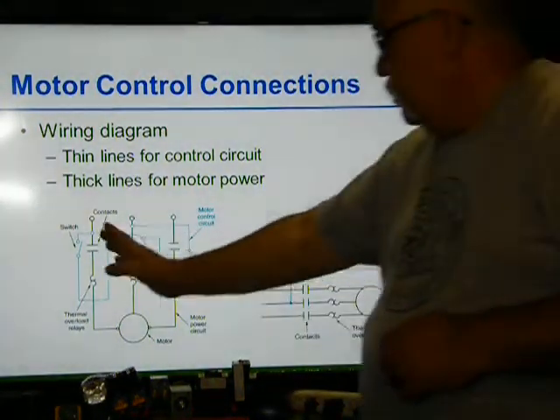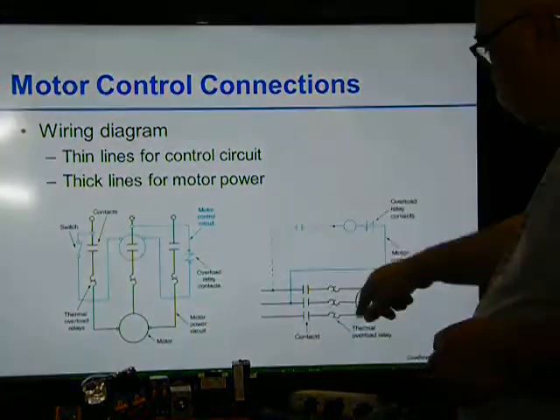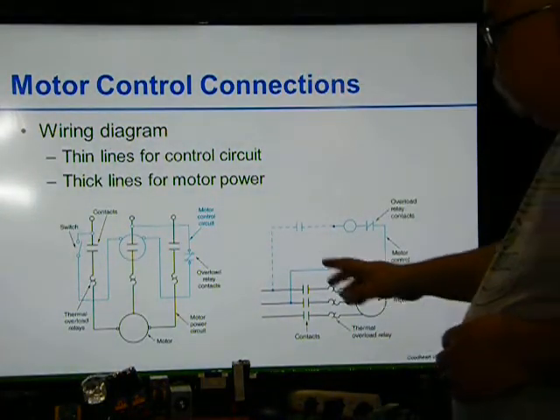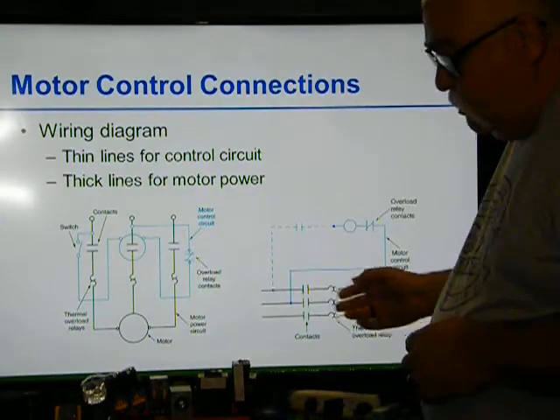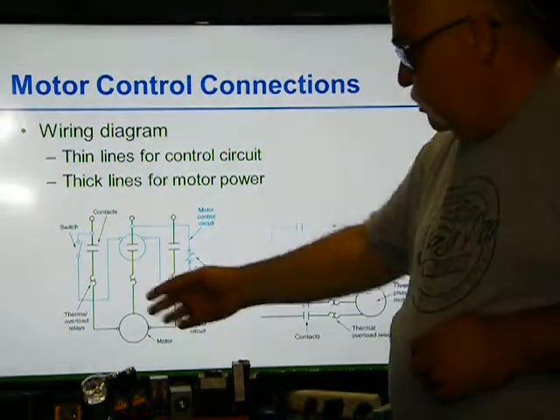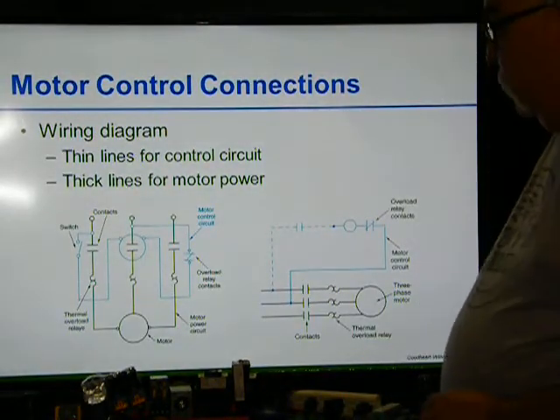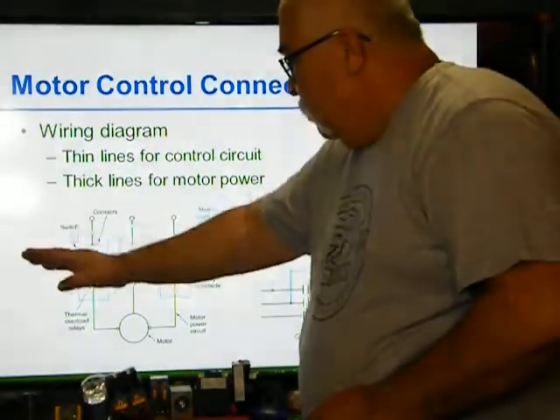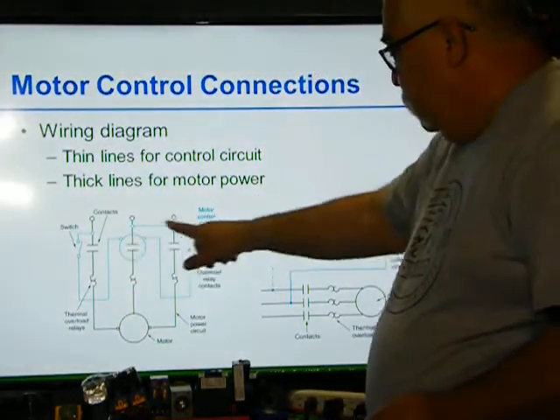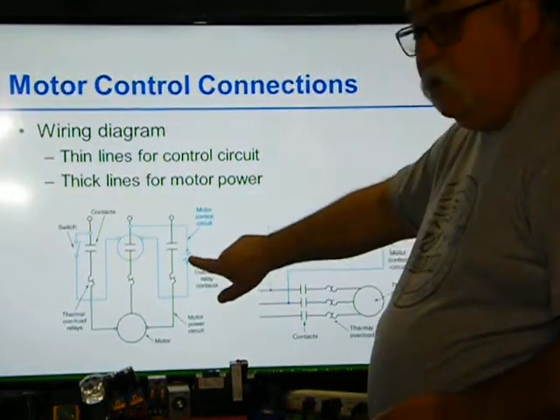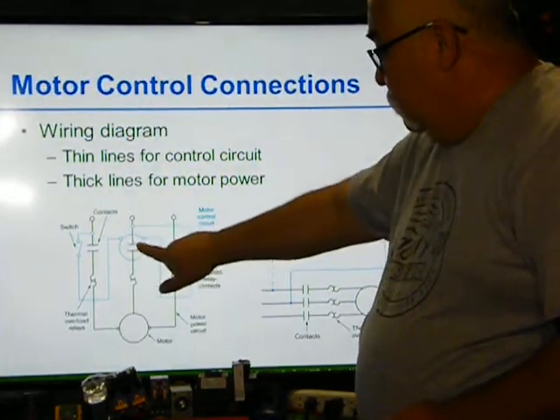Okay, with this one, I close this switch, this motor starts working. Same thing with this one. This is a 2-wire. Same thing with this one. It's the same one. It's an elementary drawing. Here's the actual. So I close this switch. Power goes to here. Guess what? This goes to this contact. This contact is always closed. Comes back to the coil.